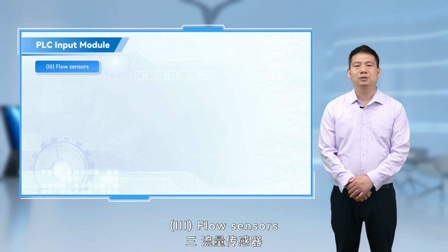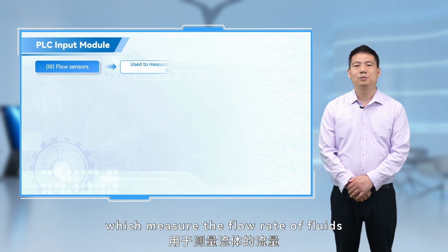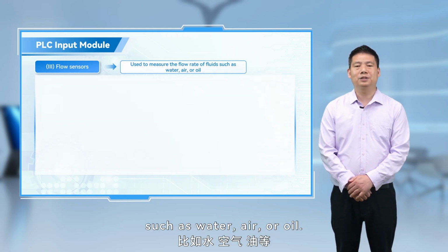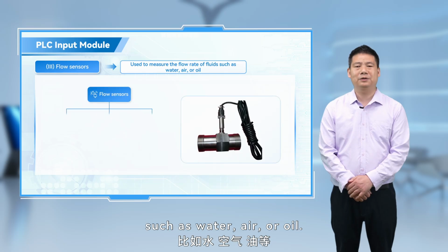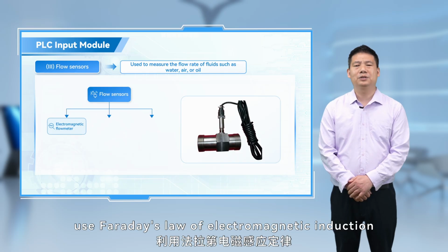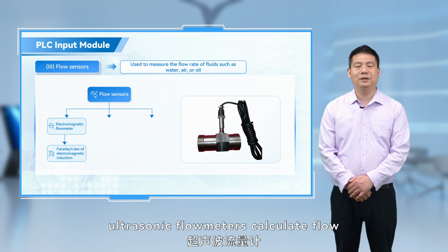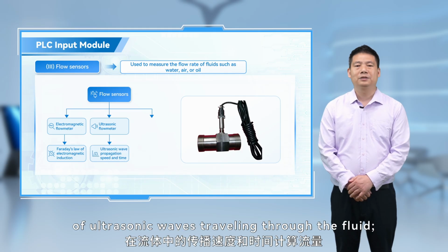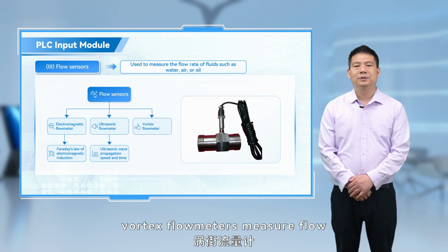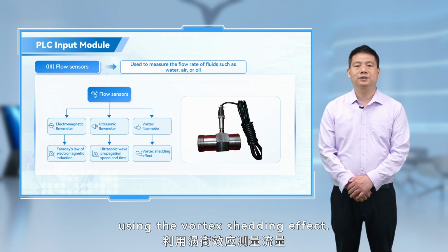3. Flow sensors. Then there are flow sensors, which measure the flow rate of fluids such as water, air, or oil. Electromagnetic flow meters use Faraday's law of electromagnetic induction to measure flow. Ultrasonic flow meters calculate flow by measuring the speed and time of ultrasonic waves traveling through the fluid. Vortex flow meters measure flow using the vortex shedding effect.